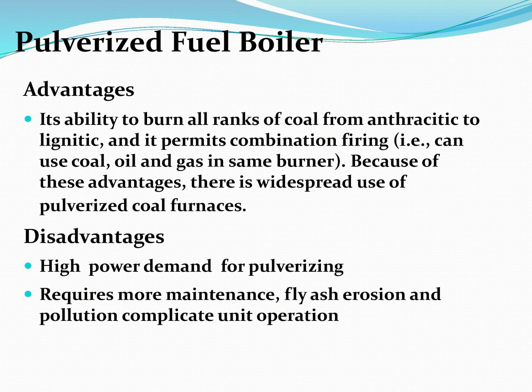Advantages: its ability to burn all ranks of coal from anthracitic to lignitic, and it permits combination firing, i.e., it can use coal, oil and gas in the same burner. Because of these advantages, there is widespread use of pulverized coal furnaces.